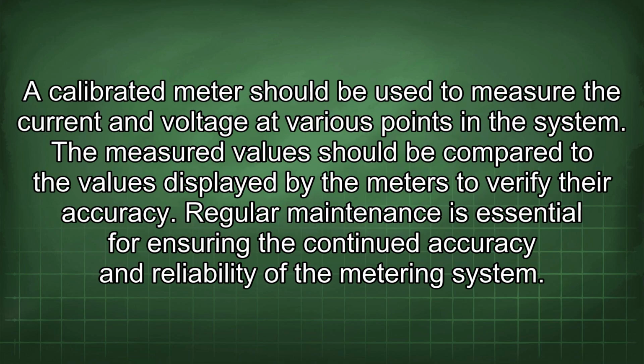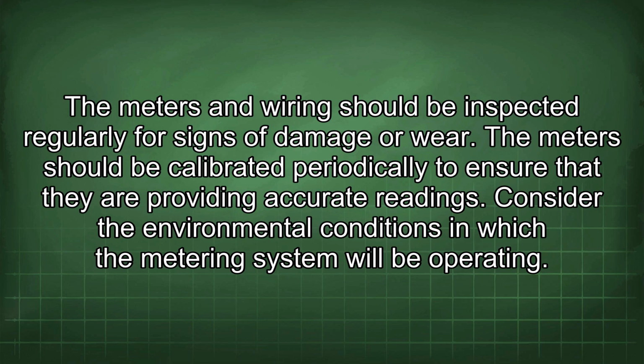A calibrated meter should be used to measure the current and voltage at various points in the system. The measured values should be compared to the values displayed by the meters to verify their accuracy. Regular maintenance is essential for ensuring the continued accuracy and reliability of the metering system. The meters and wiring should be inspected regularly for signs of damage or wear. The meters should be calibrated periodically to ensure that they are providing accurate readings.